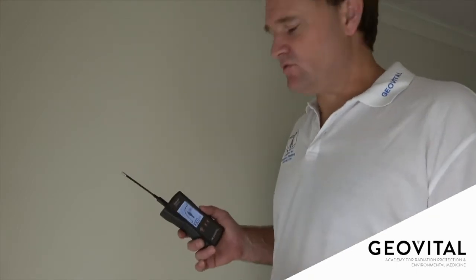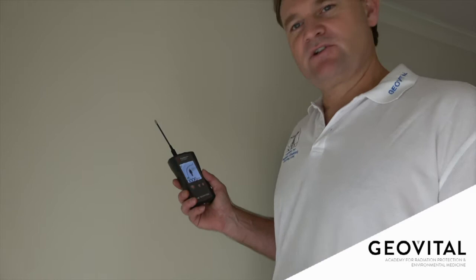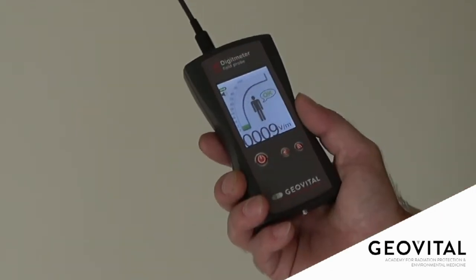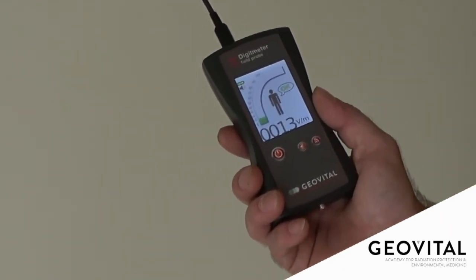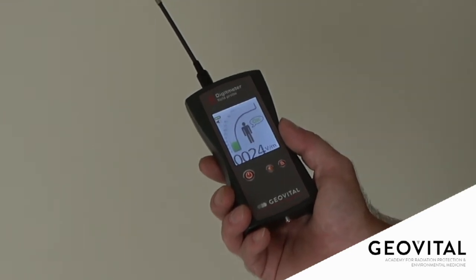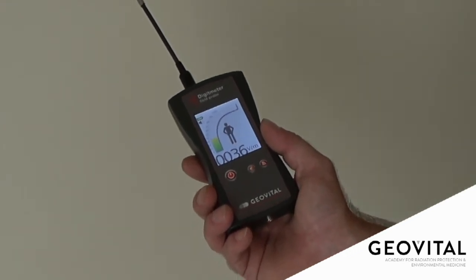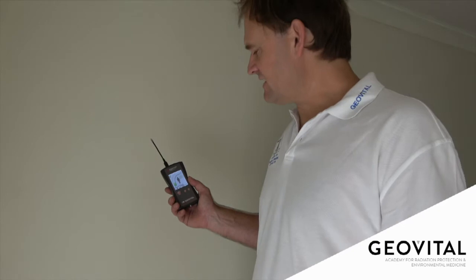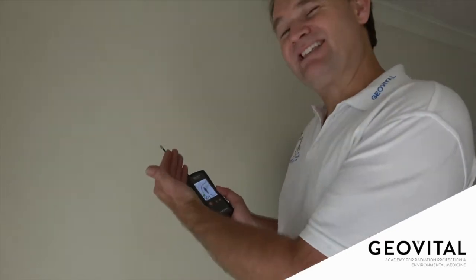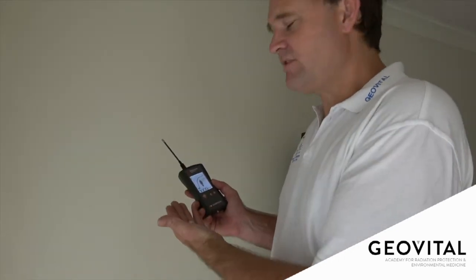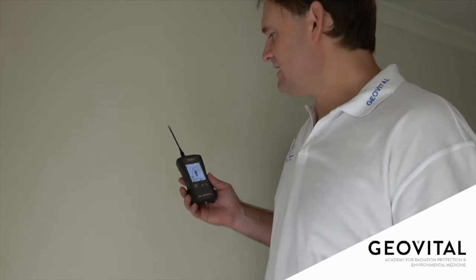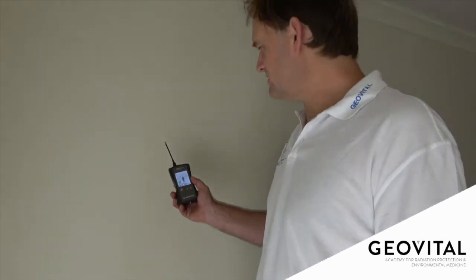Okay, with this instrument to take a measurement of, for example, the wall, we hold the instrument firmly. We can already see that we're exposed to an electric field from the wall that we're standing near, and as we get closer, of course, that value is going to go up. When we pass the 30, the Geiger counter sound starts, and when we want to measure that wall, we don't actually just touch it with the tip, we have to flatten the antenna against the wall with about a 45-degree angle between the instrument and the antenna. So just like this.